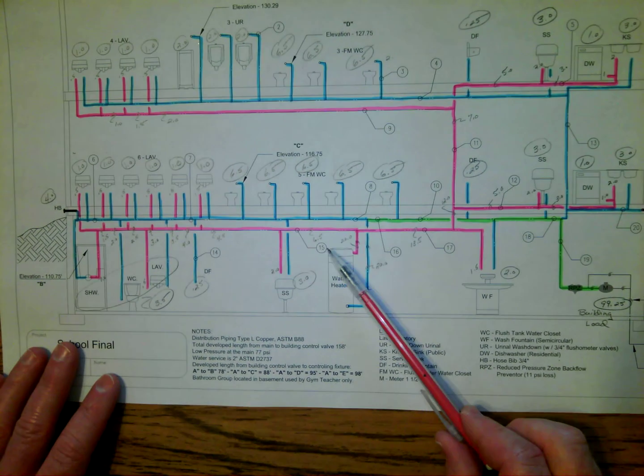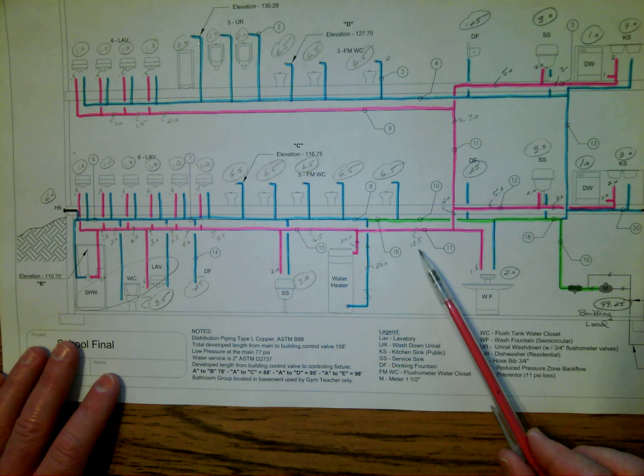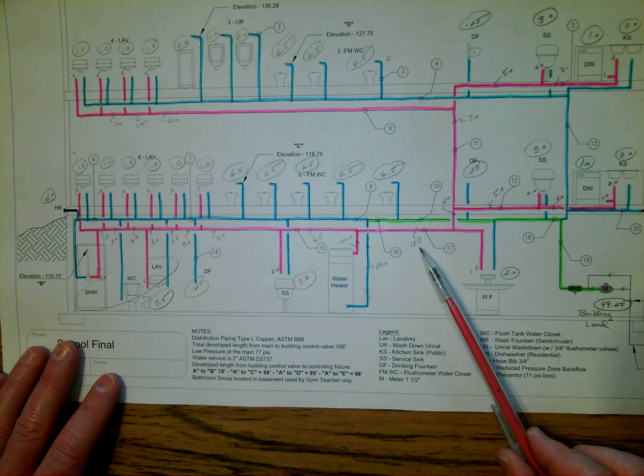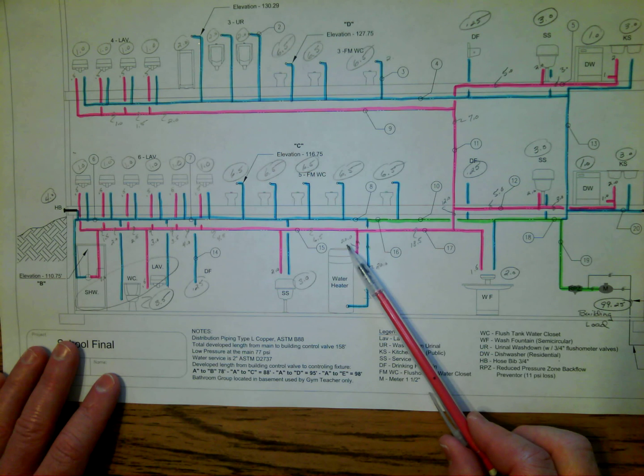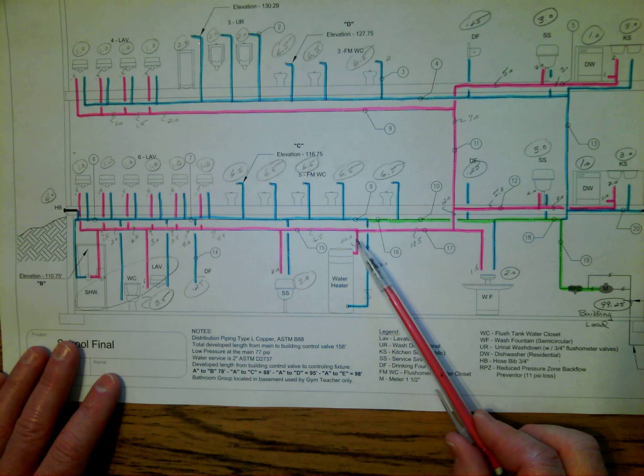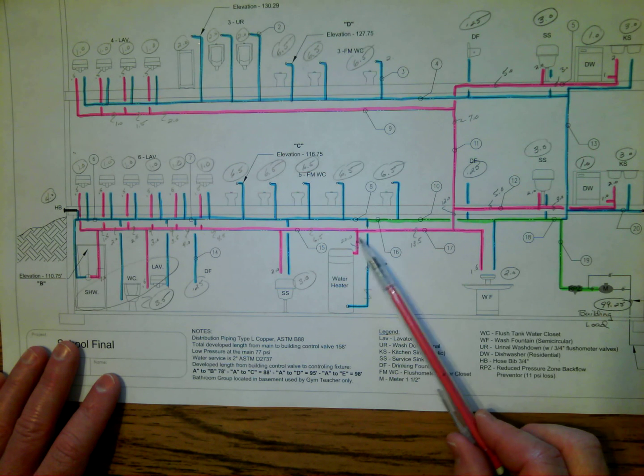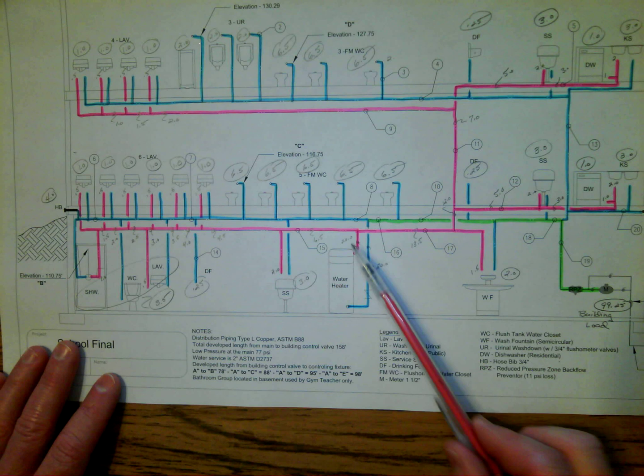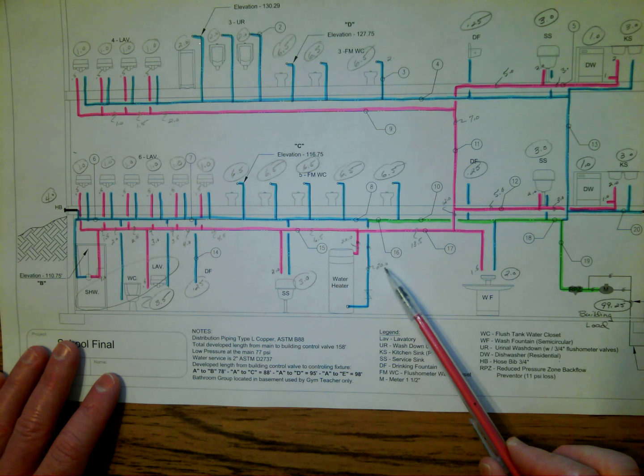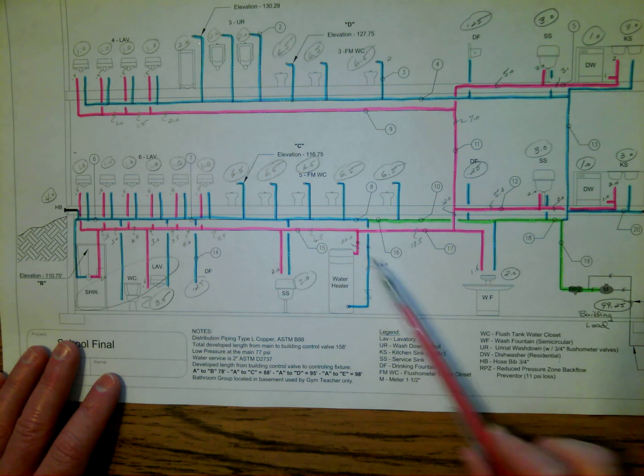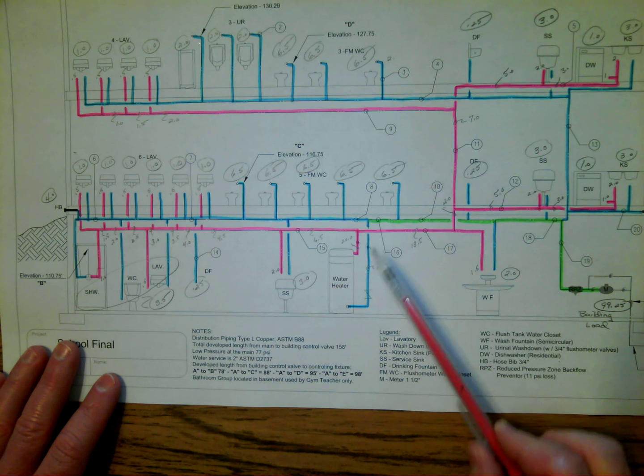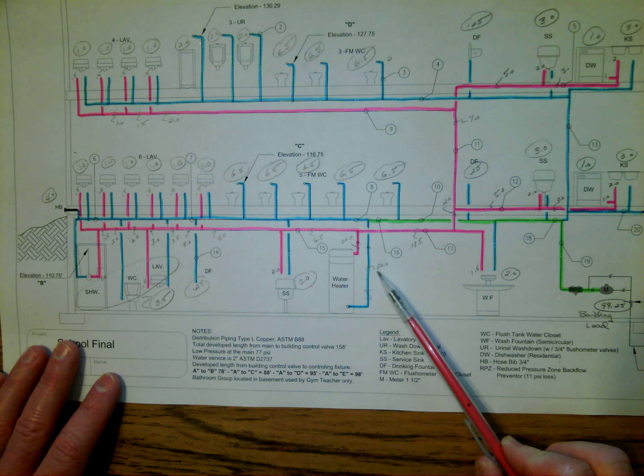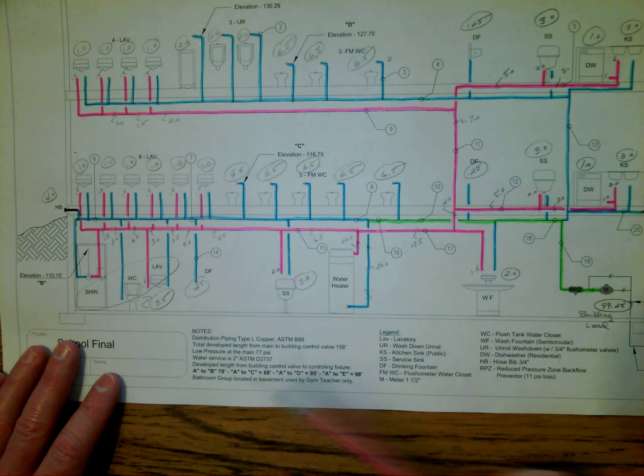That's 6.5, tied in with the 13.5 that was at pipe number 17, for a grand total of 20 WSFU. Whatever comes out of the water heater has to go into the water heater for WSFU load, so if there's 20 on this line, there would be 20 WSFU on the cold water.